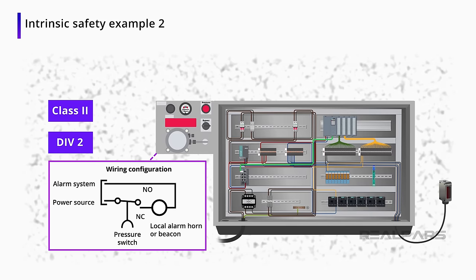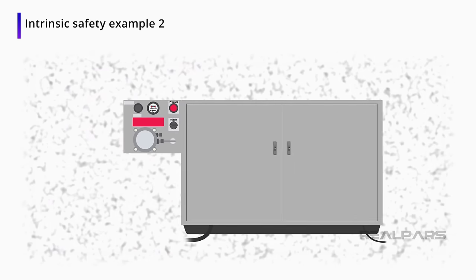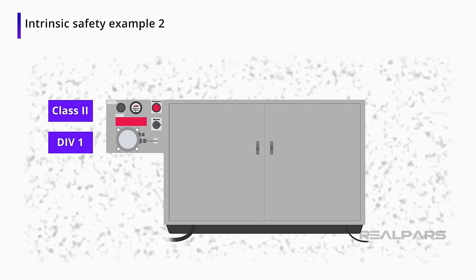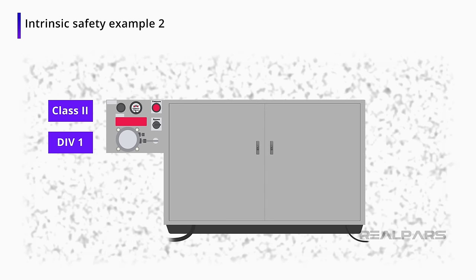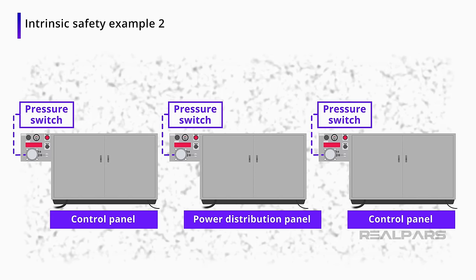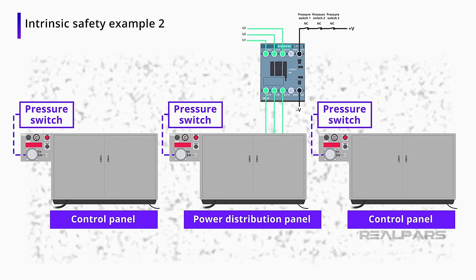When a panel is opened, the pressure switches will turn on a red strobe light, alerting those working nearby that the room is unsafe. When designing a Class 2, Division 1 panel, there are more restrictions. Division 1 refers to the presence of a hazardous atmosphere under normal operating conditions. Just like the Class 2, Division 2 environment, a Class 2, Division 1 environment will need pressure switches for loss of pressure, and will additionally need to remove line power to every panel in the room when the pressure is not safe.